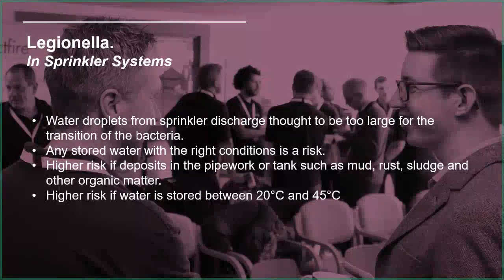Why exactly, I don't know, but I've been told that what we're looking for is water droplets less than 5 micrometers, which is 0.005 millimeters. Whereas sprinkler droplets are 200 times larger than that. So the actual discharge from the sprinkler system is too large.